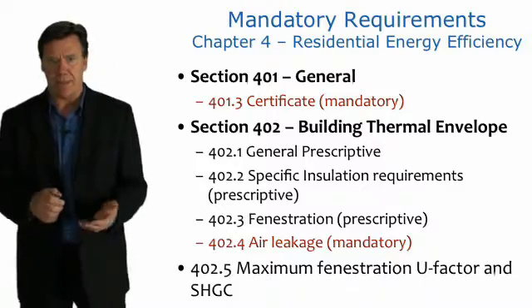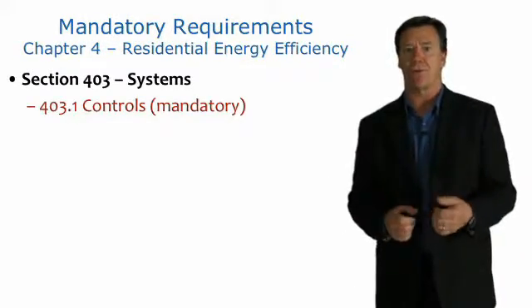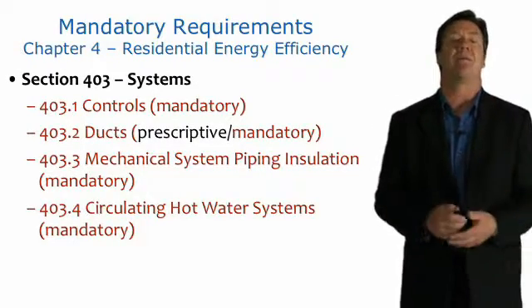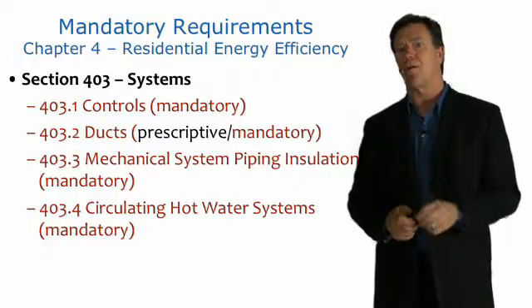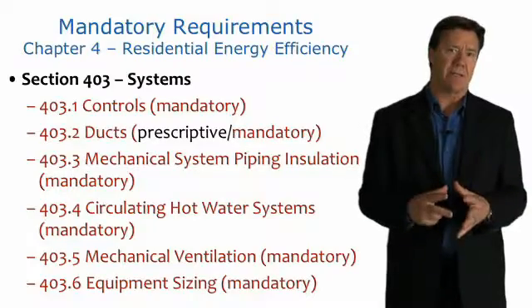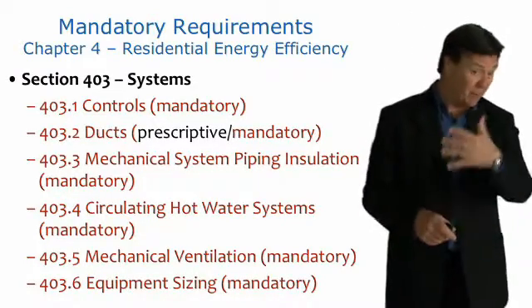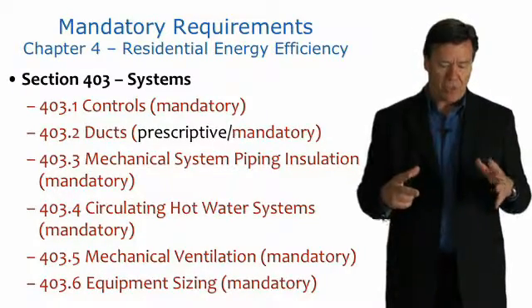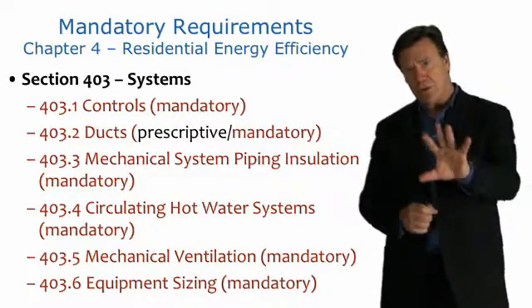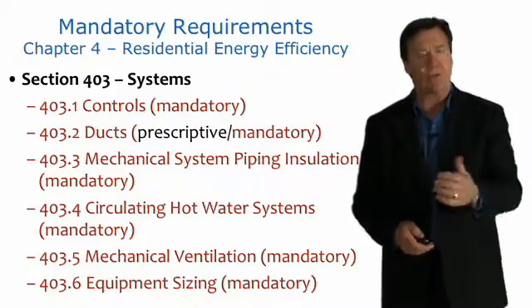With regards to mandatory requirements: a certificate is mandatory; air leakage control — sealing homes — is mandatory; controls such as thermostats are mandatory; duct sealing is mandatory; mechanical system piping insulation for hydronic systems and circulating hot water systems is mandatory; mechanical ventilation is mandatory. Equipment sizing is also mandatory, meaning heating and cooling systems must be sized appropriately using the Air Conditioning Contractors of America algorithms. Systems tend to be oversized — an oversized air conditioner short cycles, cools the house quickly but doesn't run long enough to dehumidify the air, so the house feels cold and clammy. Buildings can be more energy efficient and customers more comfortable if systems are sized and designed right.